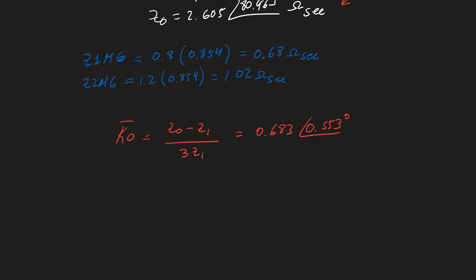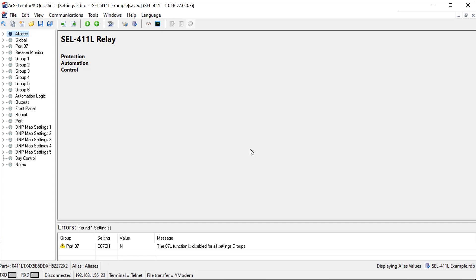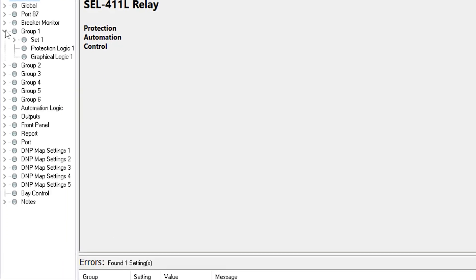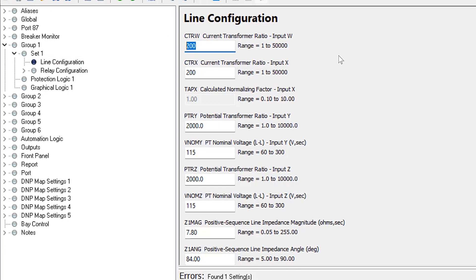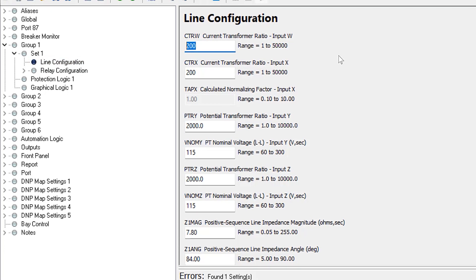Now let's program this into the relay. The settings file contains default SEL 411L settings, and we'll focus on the settings needed for the mho ground distance element. First, set up the CT ratio and PT ratio. Under group one, set one, line configuration, the CTs are wired to the W input. CTRW = 2000/5 = 400. The voltage inputs are wired to the Y input, with a PT ratio of 230 kV / 115 = 2000:1, giving a nominal secondary voltage of 115 V.